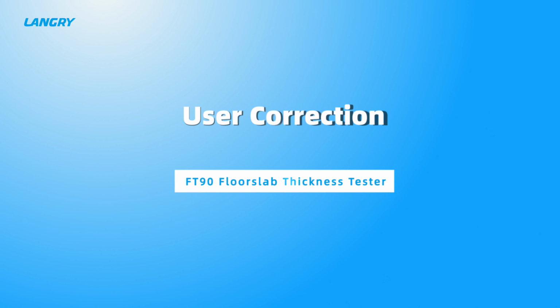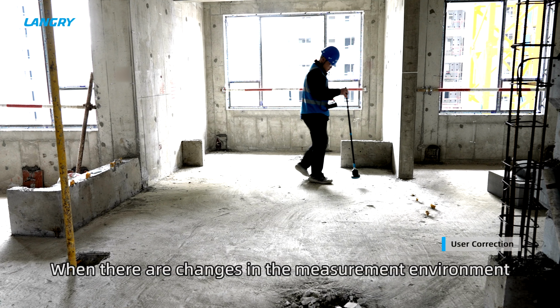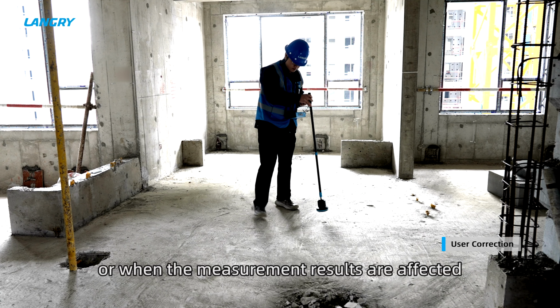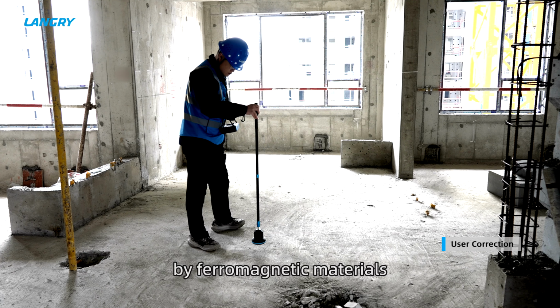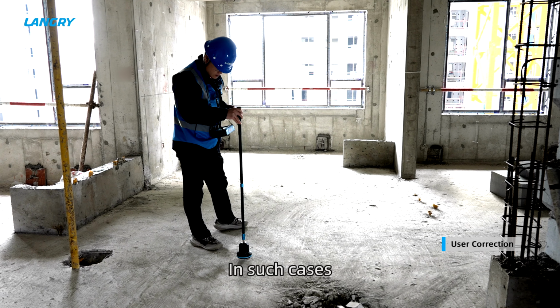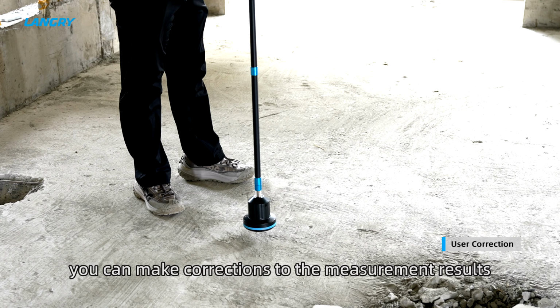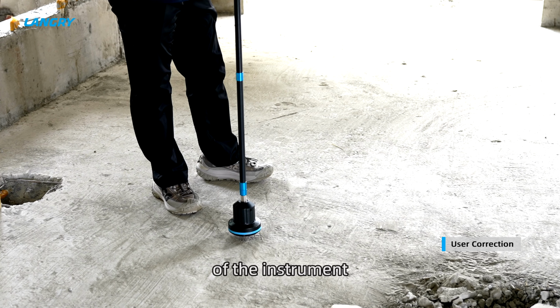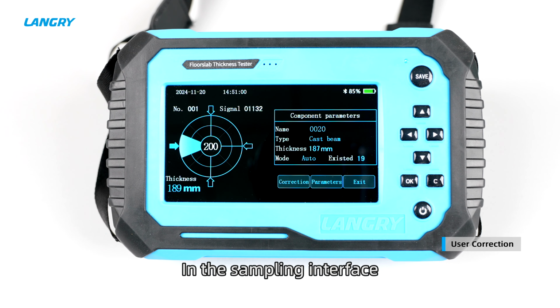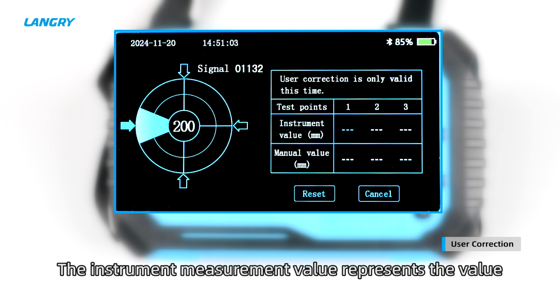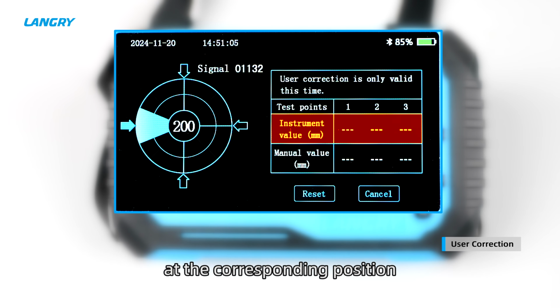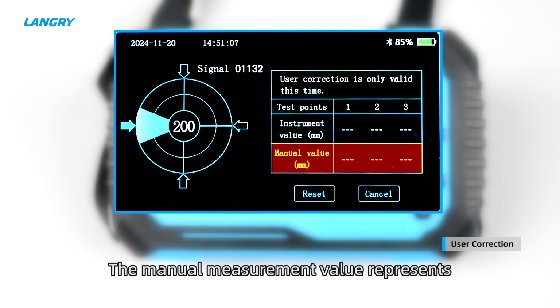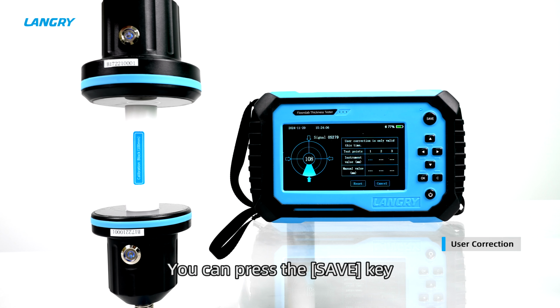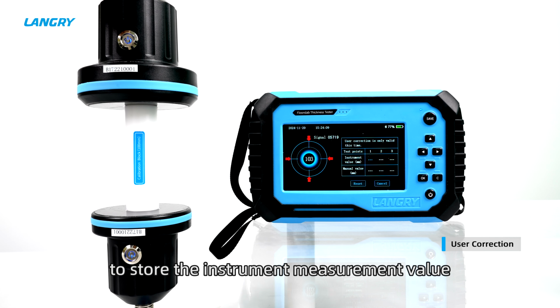5. User correction. When there are changes in the measurement environment, or when the measurement results are affected by ferromagnetic materials, there may be errors. In such cases, you can make corrections to the measurement results of the instrument. In the sampling interface, select Correction. The instrument measurement value represents the value obtained by the instrument at the corresponding position. The manual measurement value represents the true value manually measured by you. You can press the Save key to store the instrument measurement value.